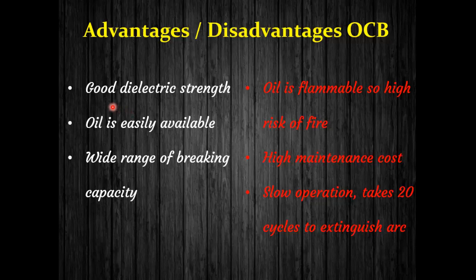The main advantages of OCBs are that oil has good dielectric strength, making it suitable for high voltage operation; oil is easily available; and the OCB has a wide range of breaking capacity. The disadvantages are that oil is flammable, posing a high risk of fire; it requires higher maintenance cost; arc quenching operation is slow, taking around 20 cycles to extinguish the arc.